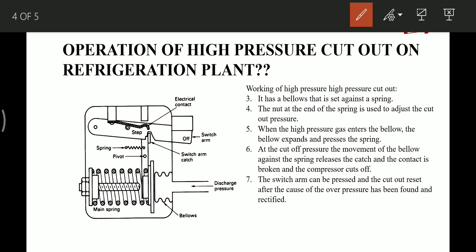As already discussed, it has a bellow which is set against a spring, this main spring. The nut at the end of the spring is used to adjust the cutout pressure. When the high pressure gas enters the bellow from this discharge connection, the bellow expands and presses the spring in this direction.